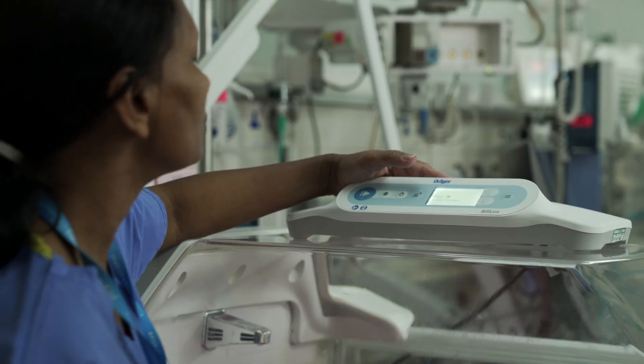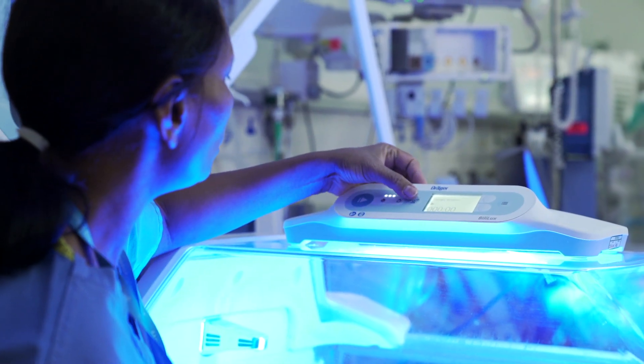The BiliLux doesn't have a fan, which actually reduces noise. Although it may not be obviously noticeable, that will definitely have a better outcome for babies, especially those receiving phototherapy for a longer time. The current phototherapy units have a fan that rotates, and that noise itself can cause harm to babies' hearing in the long term, especially when phototherapy is prolonged.